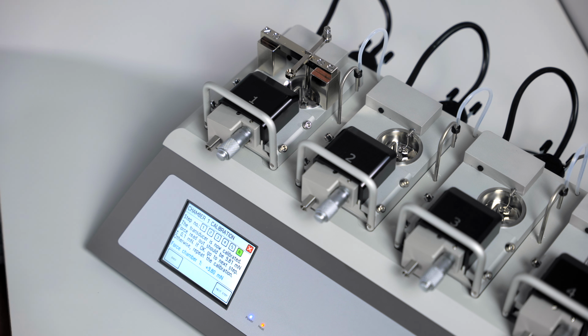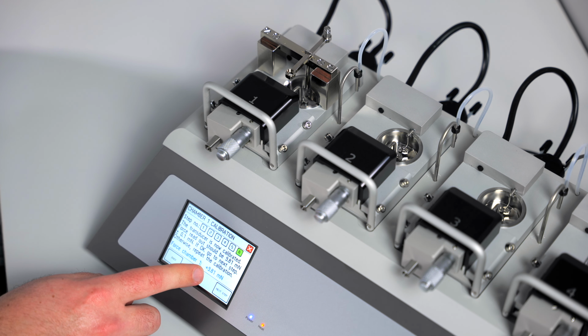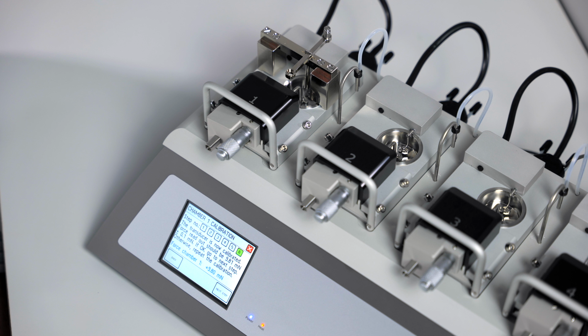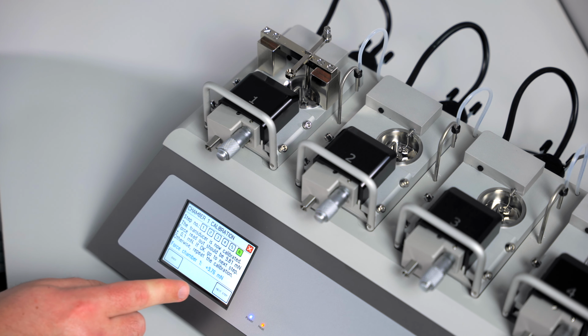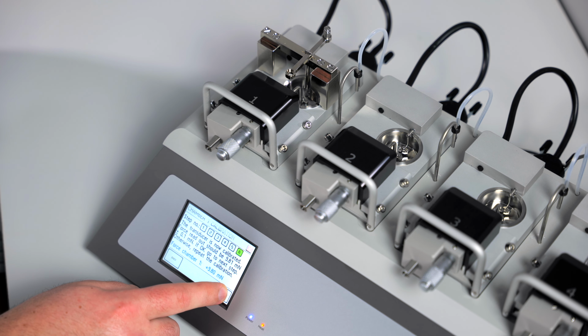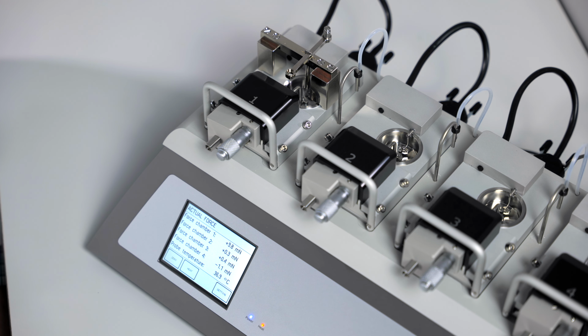Step 6 should give you a number close to 9.81 millinewtons. If you are plus or minus 0.1, you can select next step to lock in your calibration. That completes the calibration, and you can proceed to the next channel.